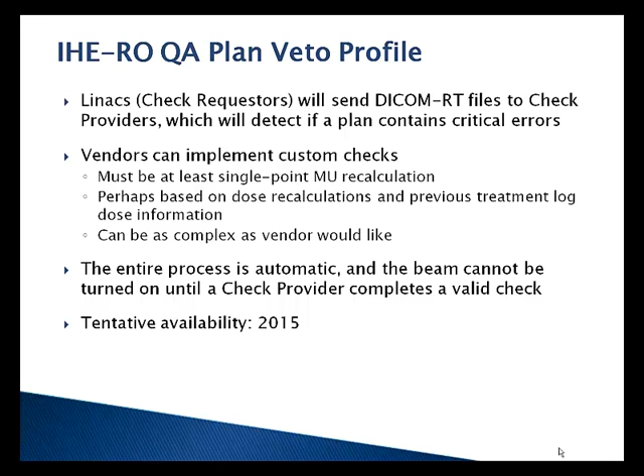So our solution will be basically all of this has to go right before we let you turn the beam on again in a manner that you specify. So this entire process is automatic, and again, it prevents the beam from being turned on. So even if you didn't notice the first fraction, your MLC didn't move, as long as your plan veto server did notice that, you won't repeat that on a patient. That's better than nothing. So we can at least only have one fraction of bad delivery. Tentative availability, this is taking a little bit longer than anyone would like, is maybe around 2015, 2016 for this to actually be in clinics.